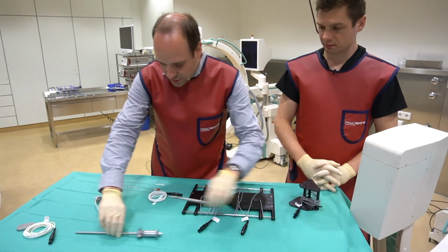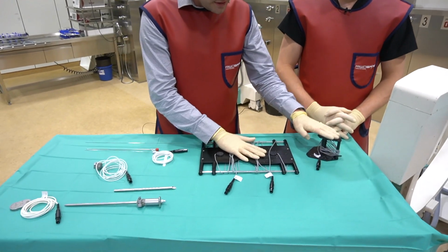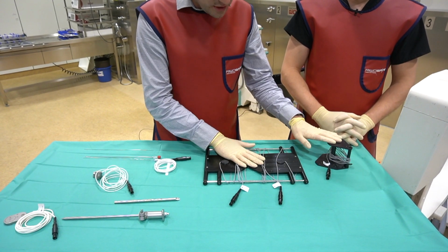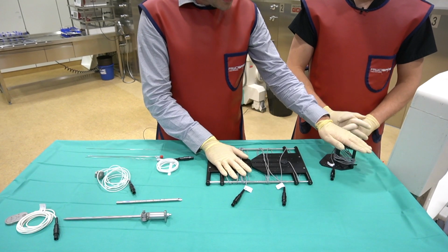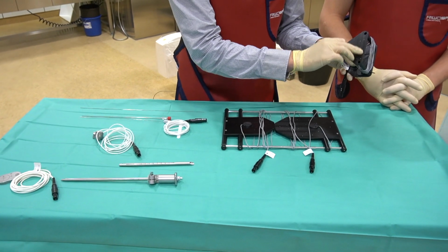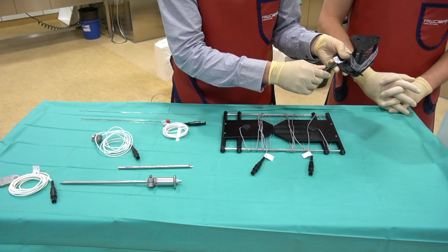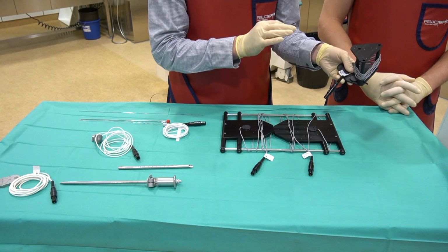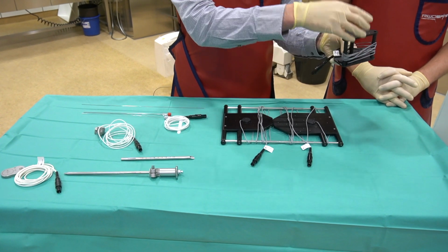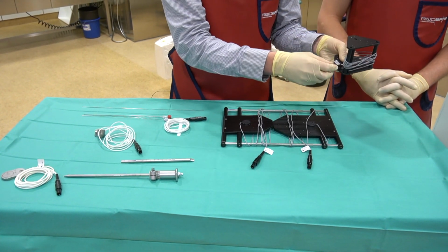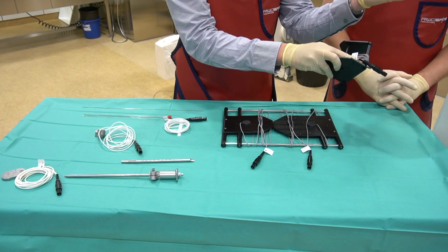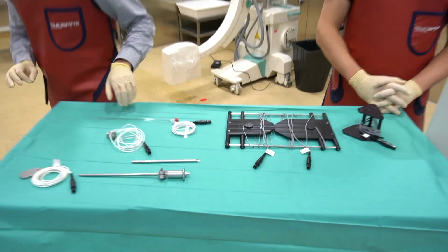I would separate this into two parts, namely these sensors. They are necessary for patient referencing. This is called the mapper bridge. This is the lateral mapper bridge, and this is the AP mapper bridge. They have X-ray opaque markers on there. They're the X-ray fiducials that we will see and that are necessary to calculate the position of this tool on top of the AP X-ray image that we see. And also here there is a positional sensor inside which we can track with the field generator.